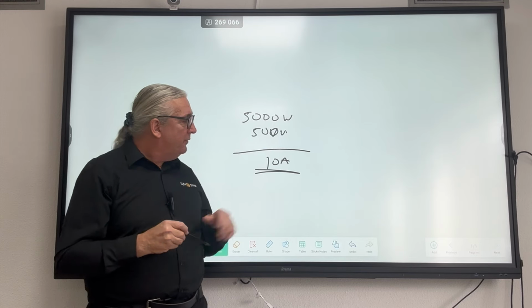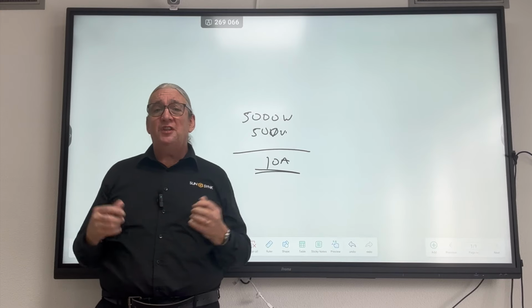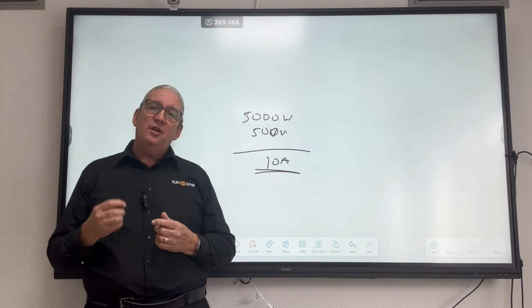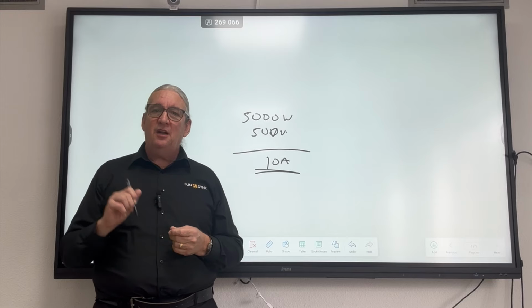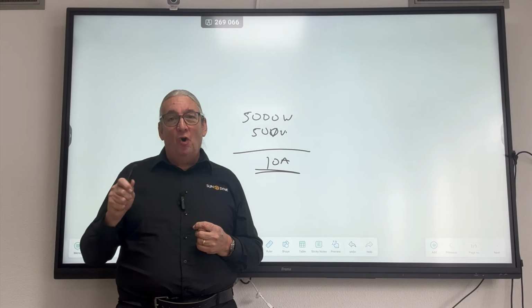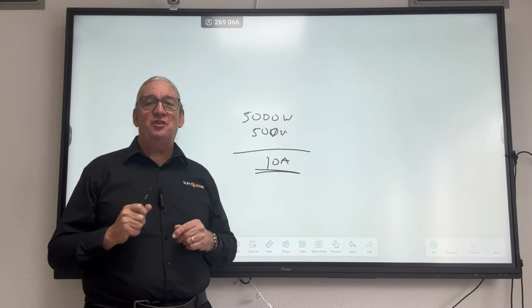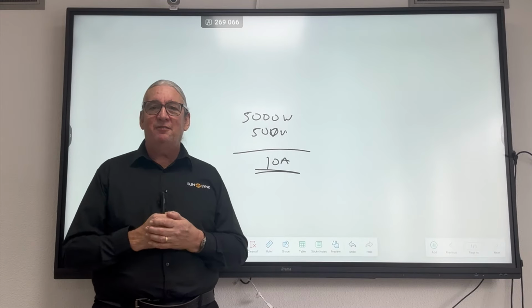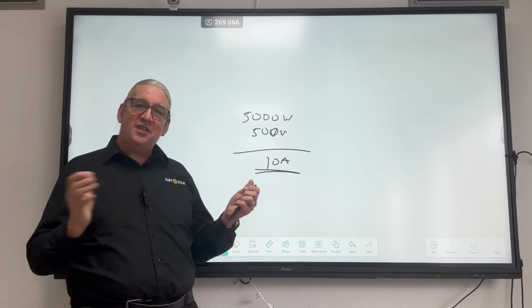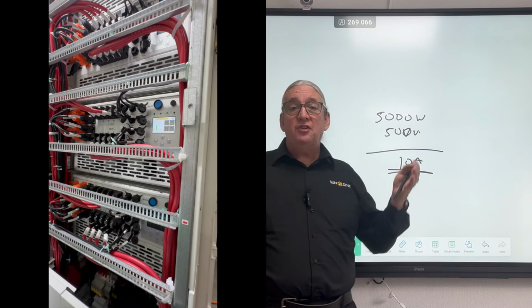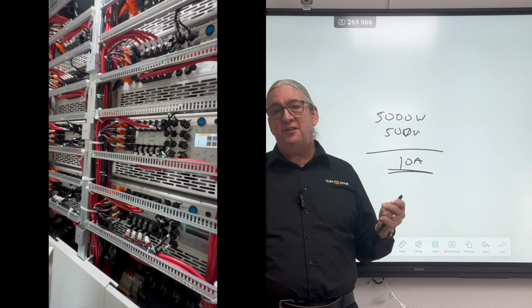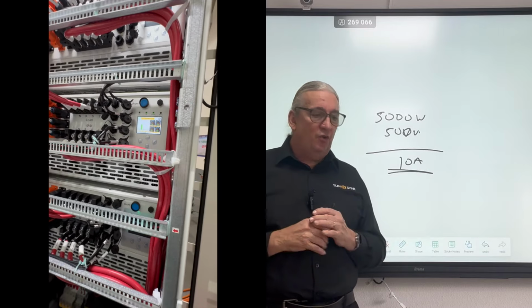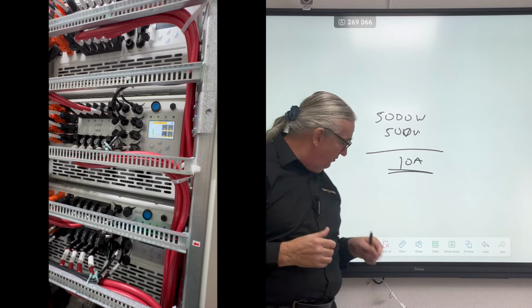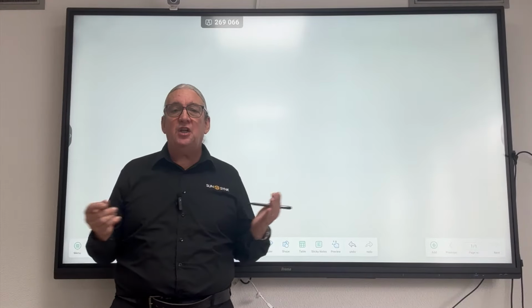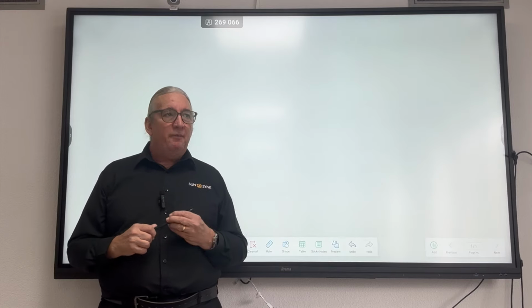At 50 volts, of course, the high current is dangerous, but you're not going to get electrocuted. However, a 50 volt low voltage inverter is much more expensive than a high voltage inverter. So with Sunsynk, we actually do both. For the big systems, going up to 50 kilowatt or 100 kilowatt, it has to be high voltage - that's what we use in the gate and the containerized systems, because the currents are so high you can't justify low voltage. And then there are other problems to do with battery imbalancing, which we're not going to talk about now.